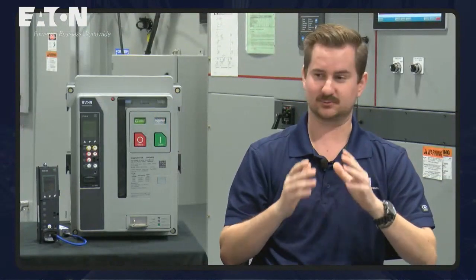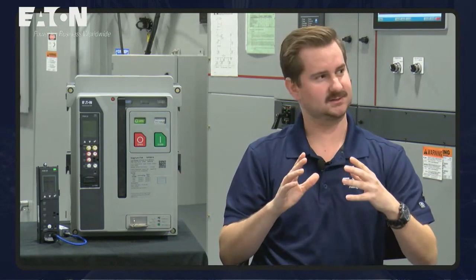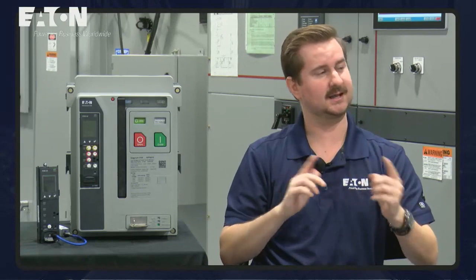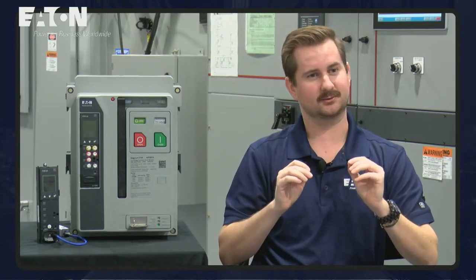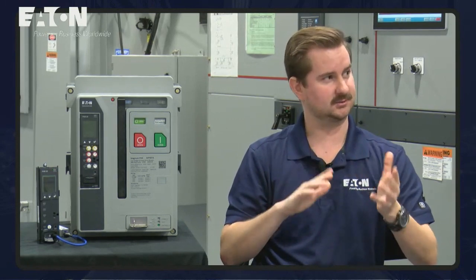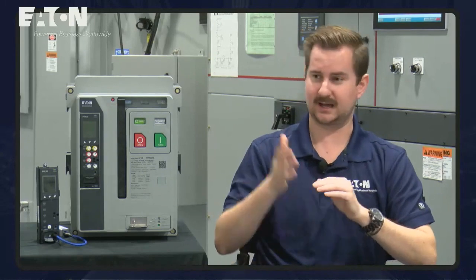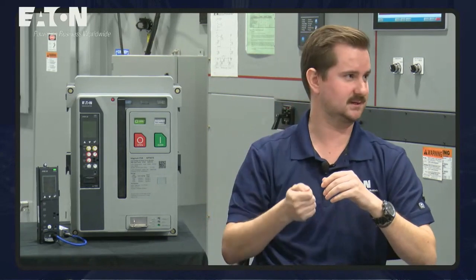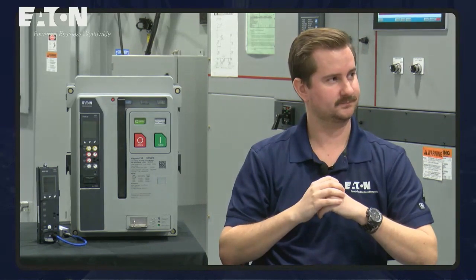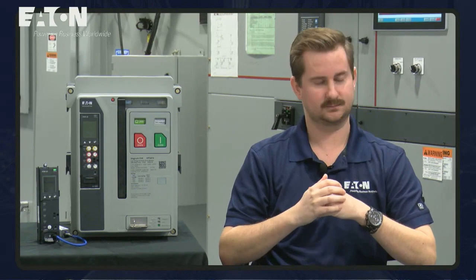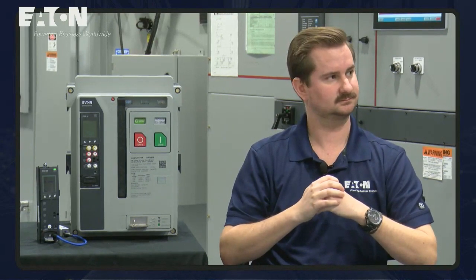Yeah, so MR2 is our industry-exclusive motorized remote racking device. It's really cool. It actually sits inside of the breaker, and it's all integrated within it. So it allows you to remotely rack the breaker in and out of the cell, and it's done through a pendant, through one of Eaton's dashboard products, or through discrete controls. Naturally, you can control multiple breakers with a single pendant and all sorts of other things. It's very, very neat. Okay, that's really cool. That's very similar to what we have in our medium voltage switchgear. Precisely.